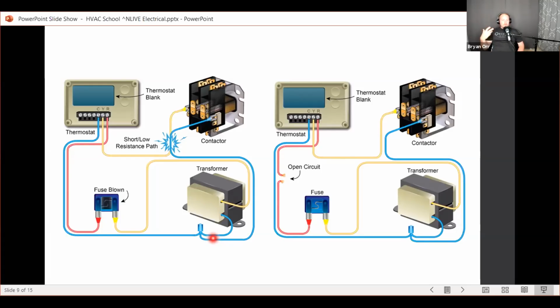You ruin the battery. When you short out something like a transformer or the high voltage into your house, you have a much greater power supply because ultimately it's connected all the way back to the power plant. And so in order to get it to shut off before it just melts everything all the way back, you have to have these overloads. You have to have these fusible links. You have to have these circuit breakers that break the circuit so that it doesn't damage the wiring. And that's in this case what our fuse does.